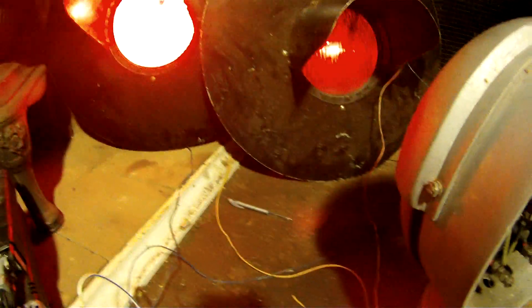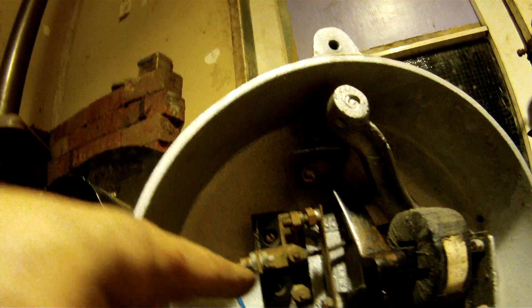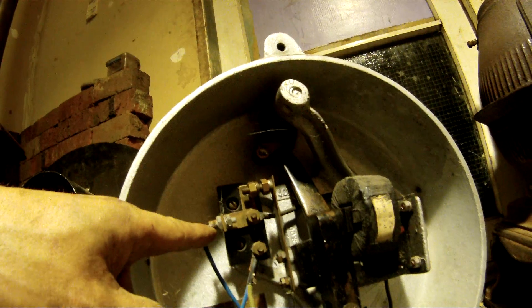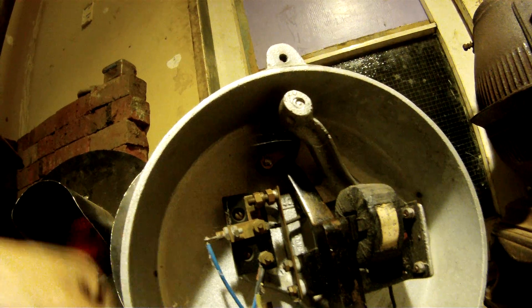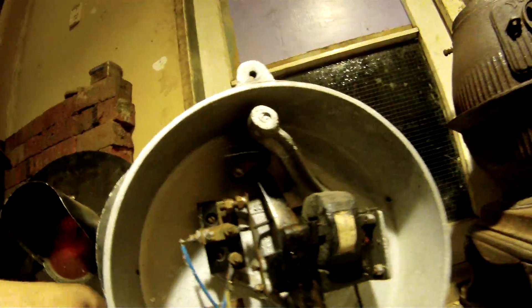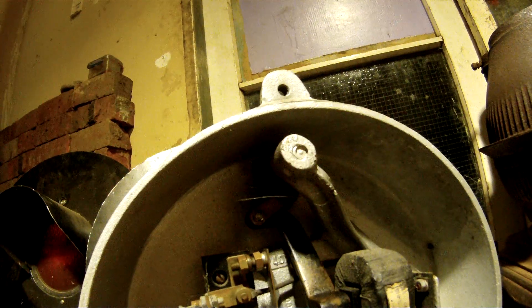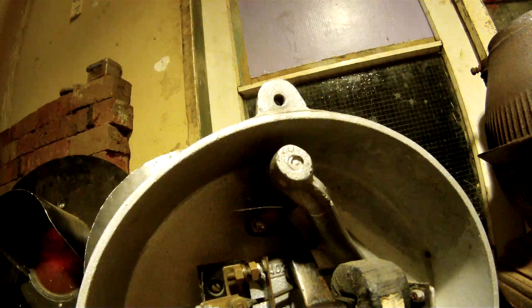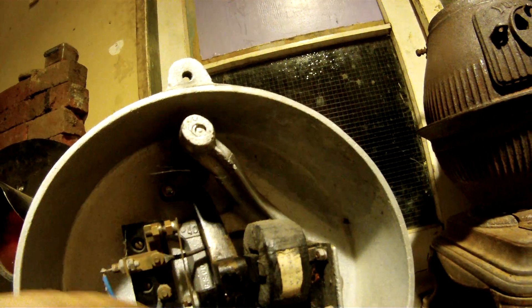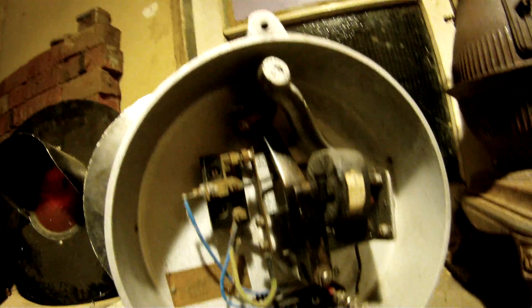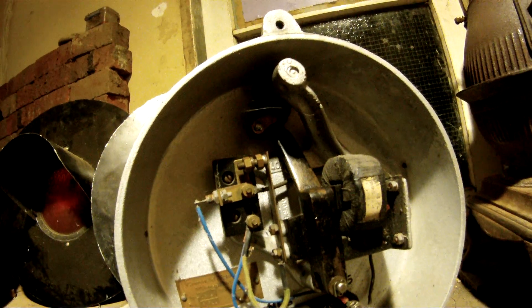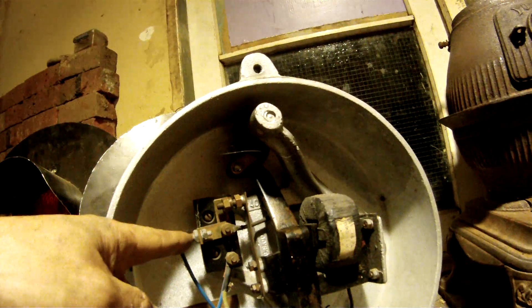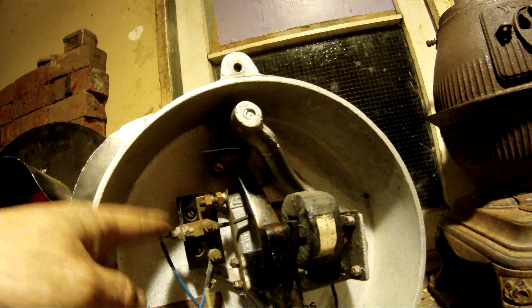Let's turn these blinding little buggers off. That there is a diode. Now it's connected up in reverse along with your power supply. Now every time these contacts open, it makes a high voltage kick which can go back through your line and damage your control equipment. So that's why they have that diode in there.